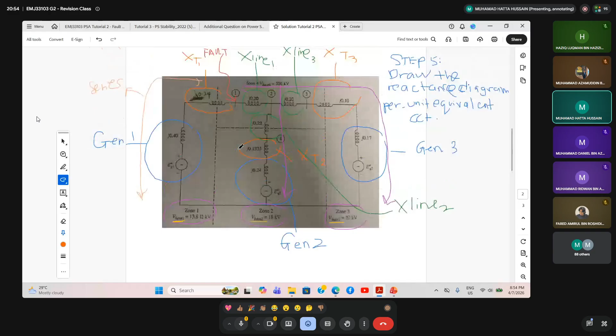So you take 525 kV, the pre-fault voltage, and divide it by the nominal voltage value, which is 525 divided by 500, giving us 1.050 per unit at 0 degrees.